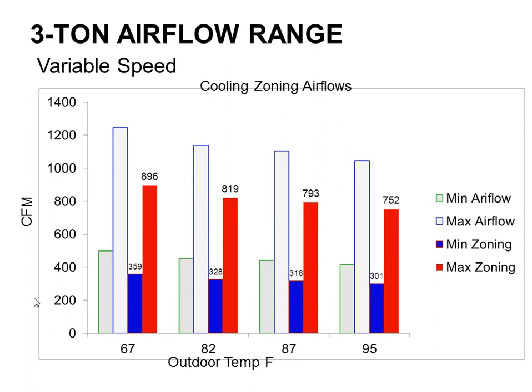So here's what would happen on a zoning system. Not only can I cut down the airflow more because I have the variable speed compressor, I'm also allowed to cut it back even a little further with the zoning system. So instead of a 60% reduction, I can get even down to like a 70% reduction in airflow. In this example, going from like 1100 CFM down to 350 CFM on a normal type cooling day. This guy is very, very adaptable to zoning systems. It would be the preferred type of condensing unit / heat pump that you would put on a zoning system. None of our other units would be able to operate on this low of an airflow condition.